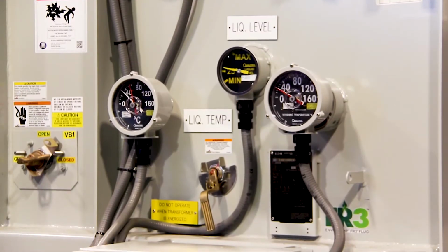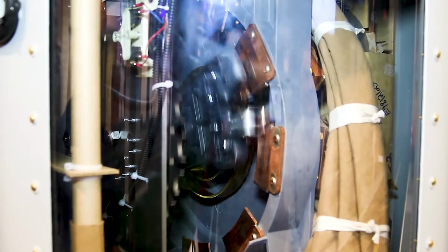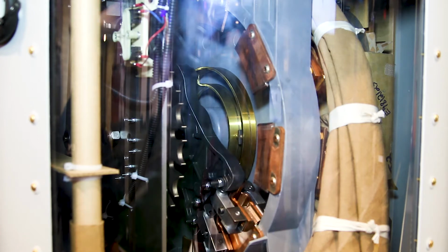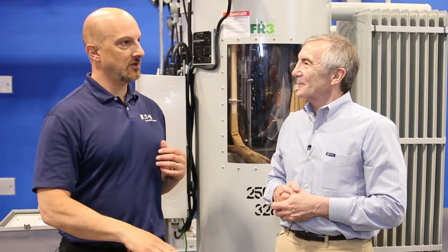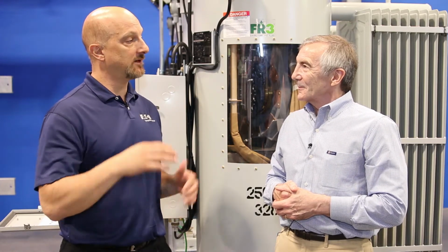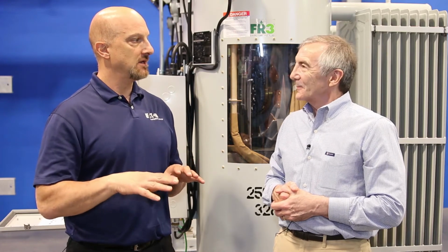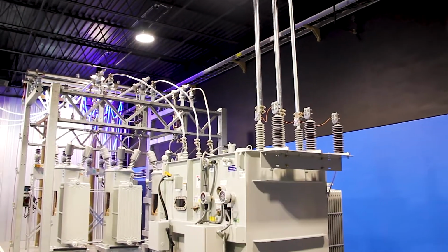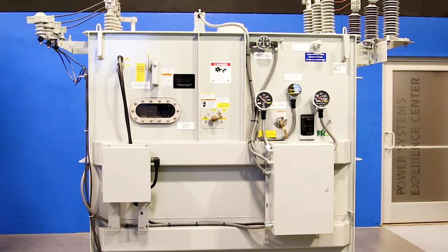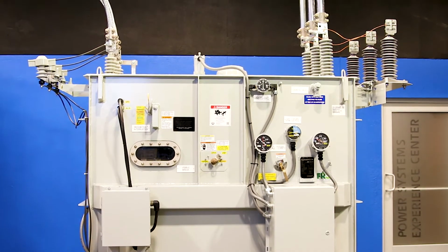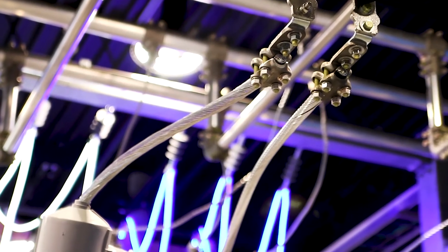So these things that we're standing right next to are regulators, and the regulators get a little bit confused. Do I need to go back up or do I need to go back down? And then a cloud comes by and the solar goes away and the regulators are low and the voltage is all over the place. So we have issues with three main components. One are the capacitor banks that supply the reactive power to maintain voltage stabilization. The other are the regulators that truly regulate the voltage. And the third is the capacity of the transformers and the other equipment, the wire sizes and so forth. They're rated for a certain amount of current, and the more we put into the substation, we may put more current in than they were even rated for.